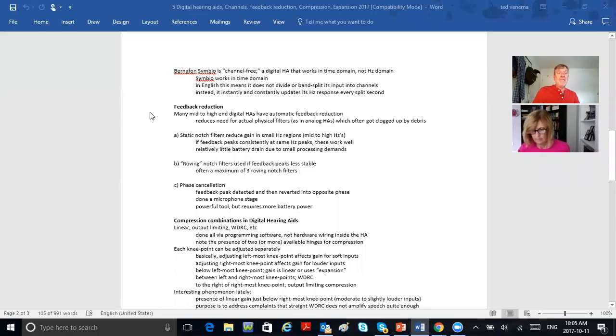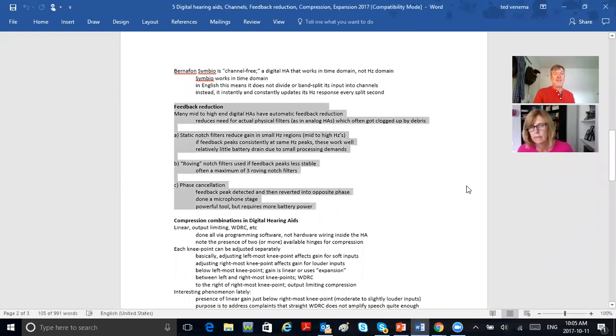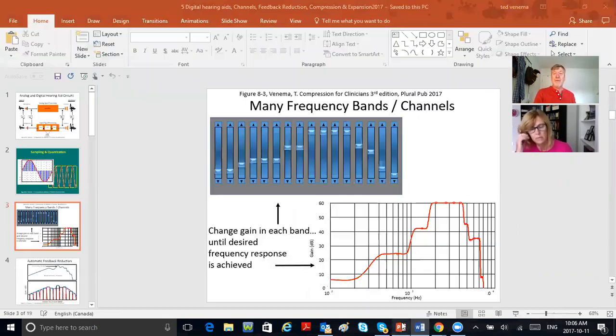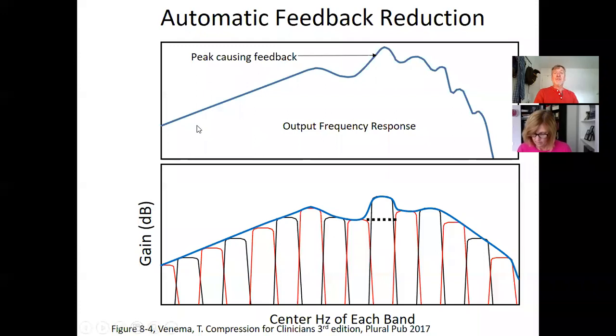How do they get rid of feedback? Many mid- to high-end hearing aids have automatic feedback reduction — very common, found in almost all digital hearing aids today. It reduces the need for actual physical filters, as analog hearing aids used to use. Here's a feedback reduction slide: a fictitious frequency response showing more treble amplification because most people have trouble hearing treble.